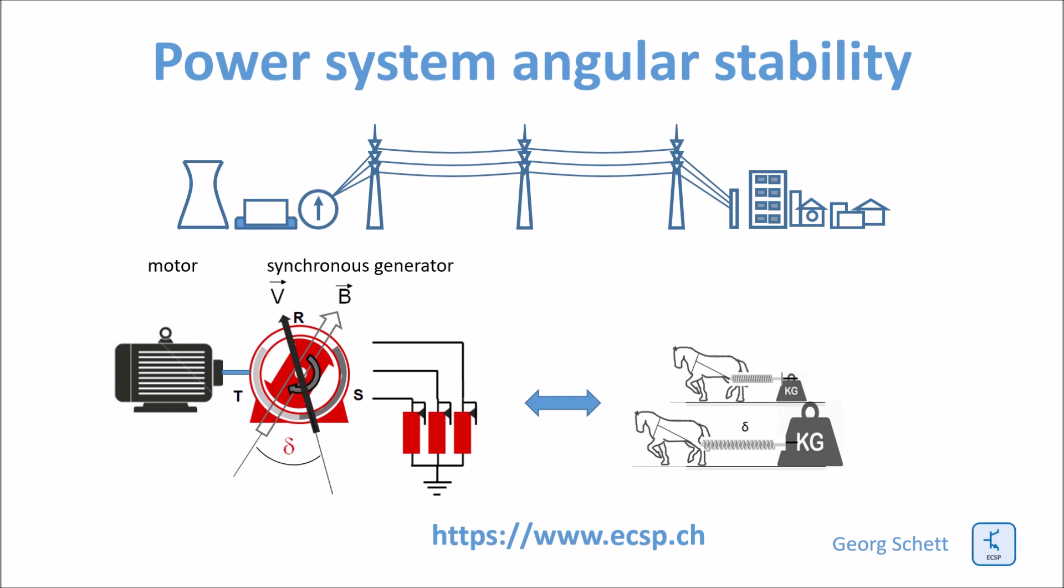As soon as the generator supplies real power to the network, there will be an angle between the rotating magnetic field of the stator of the generator and the DC magnetic field of the rotor. This angle is proportional to the torque which is applied by the motor connected to the shaft of the generator.